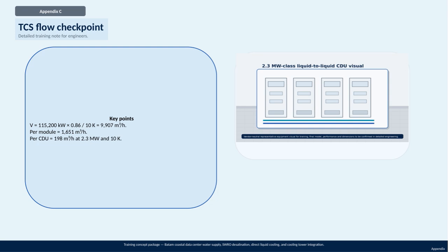The total flow volume, V, is calculated as 115,200 kilowatts multiplied by 0.86 divided by 10 Kelvin, which results in 9,907 cubic meters per hour. Breaking that down further, each module handles a flow of 1,651 cubic meters per hour, and each cooling distribution unit, or CDU, manages 198 cubic meters per hour at 2.3 megawatts and with a 10 Kelvin temperature difference.